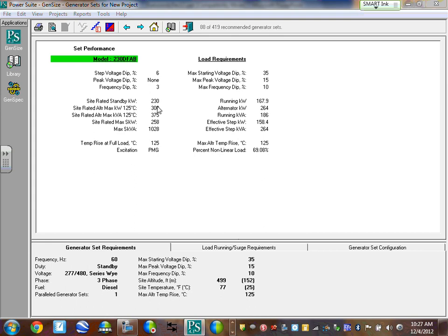Okay. They used to give a percentage of this, so those are the two figures to look at. That's not bad. That's a good size for this model. I like keeping that ratio, 167 to 230. The total running KW is, we'll call it 170, to 230. About 70% of the load is a good size. That allows the customer in the very end to add load. They're all going to do that. They're going to put some things that they don't even have yet on emergency. At some point during time, they might buy more equipment. So it's always good to go 70% starting out.